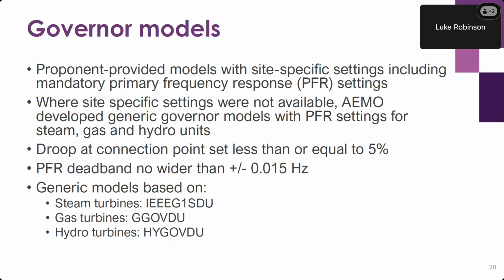So this includes, for example, that the droop at the connection point must be set to less than or equal to 5%. When operating at maximum power, we don't expect any further frequency raise response from the generator, and the primary frequency response deadband should be no wider than plus or minus 0.015 Hertz. So the generic models were customized for each generator by adjusting the maximum and minimum power output limits, and the following PSSE library models were adopted, as you can see there on the screen.